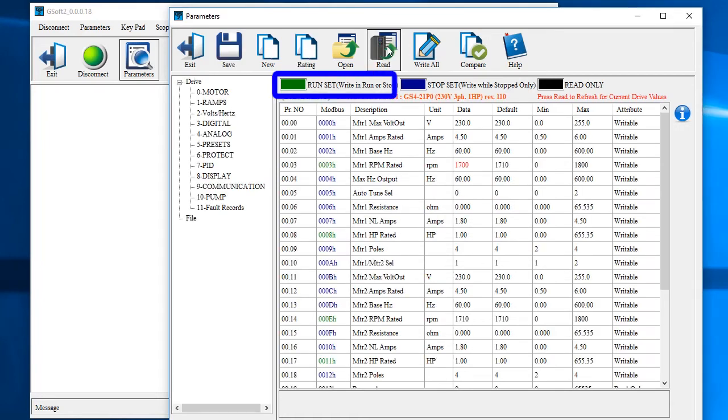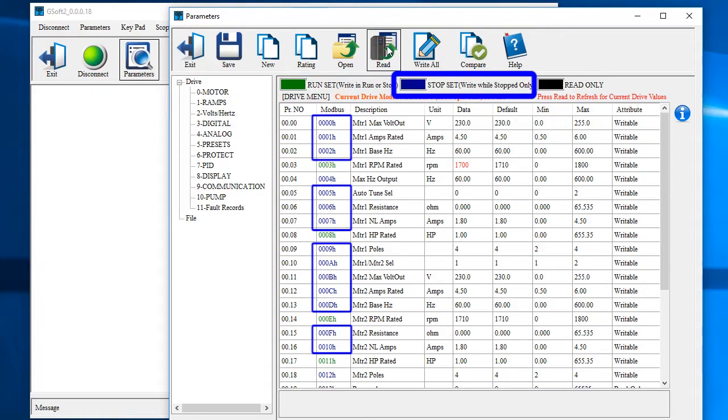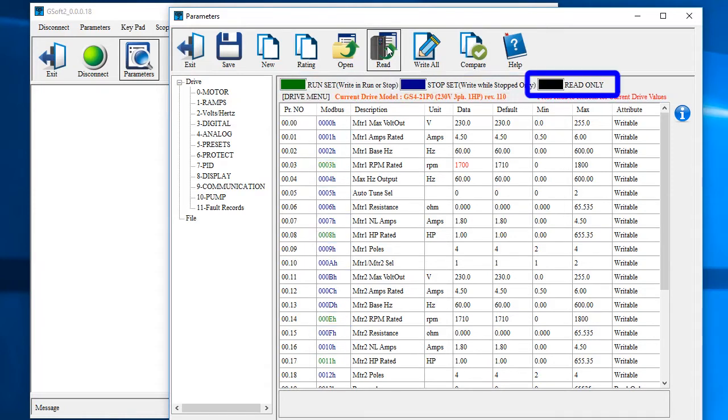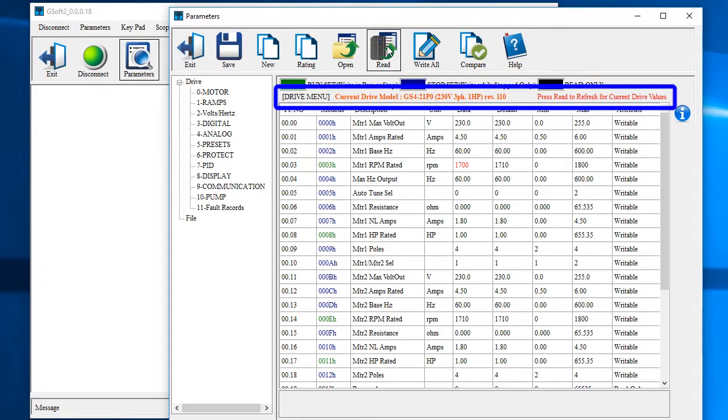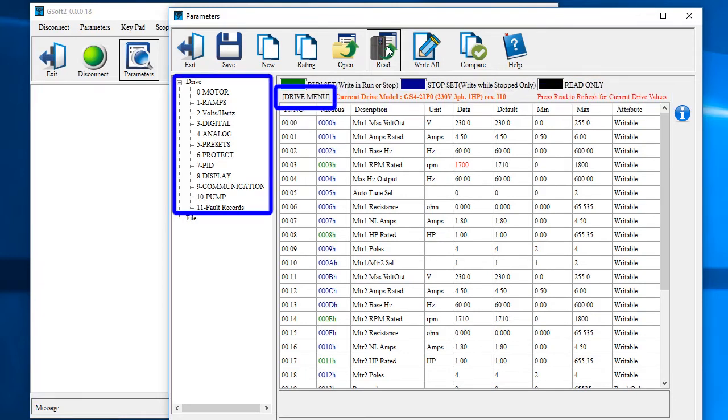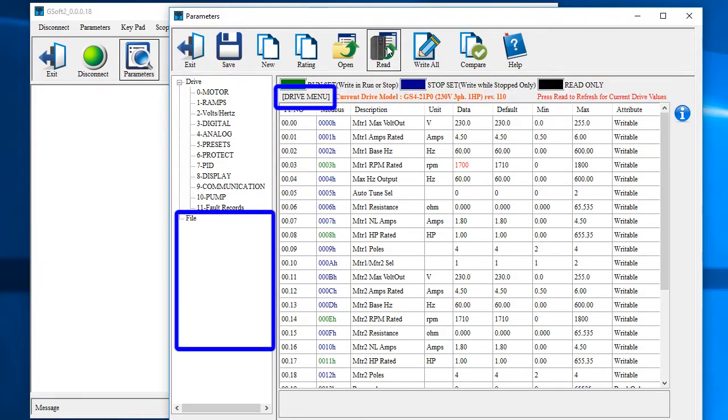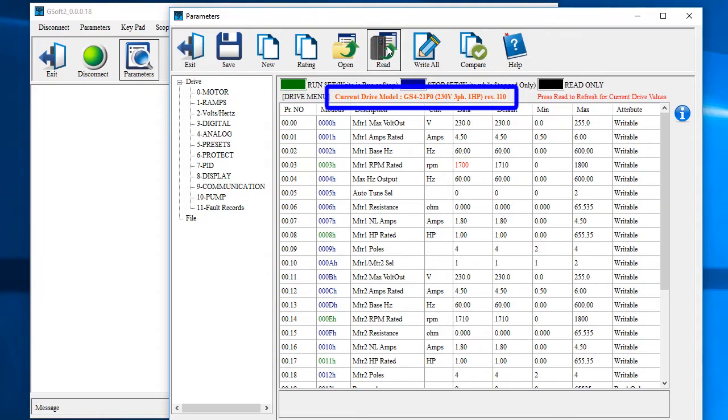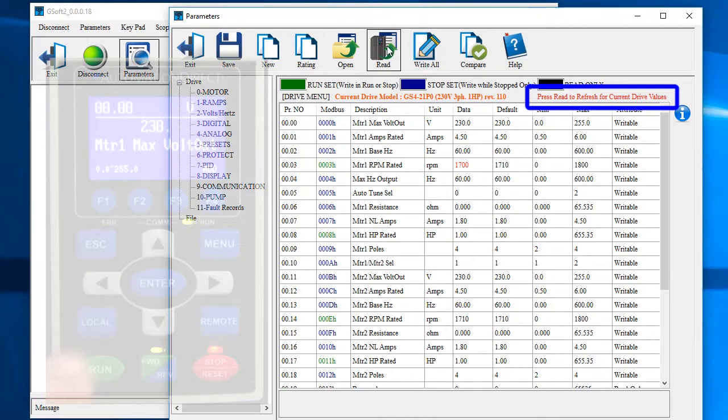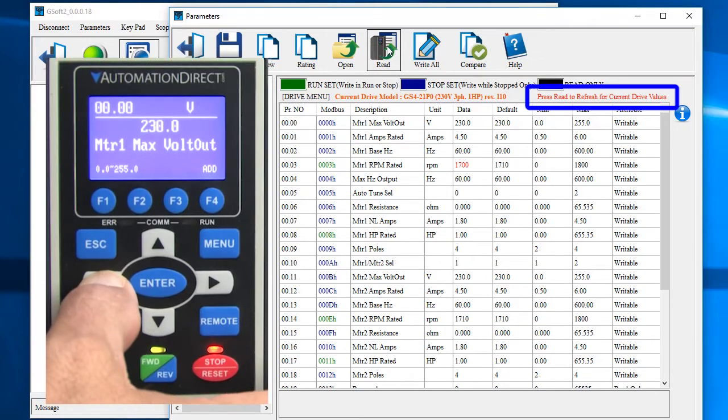This tells us that green parameters can be written to while the motor is running. Blue parameters can only be written when the motor is not running and black are read only parameters. This line is important. It tells us we are currently looking at the drive menu, not the file menu, which drive GSoft 2 thinks we are playing with and a reminder to hit the read to update the current drive parameters.